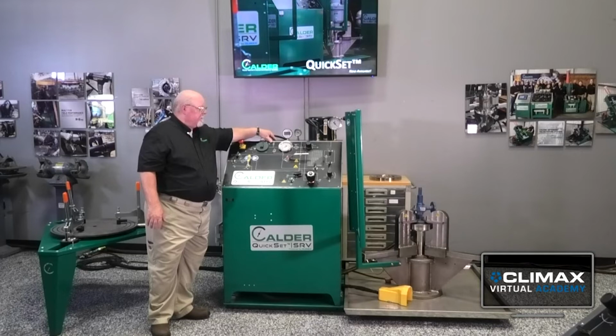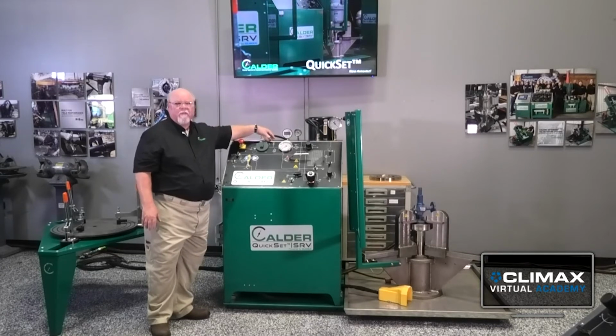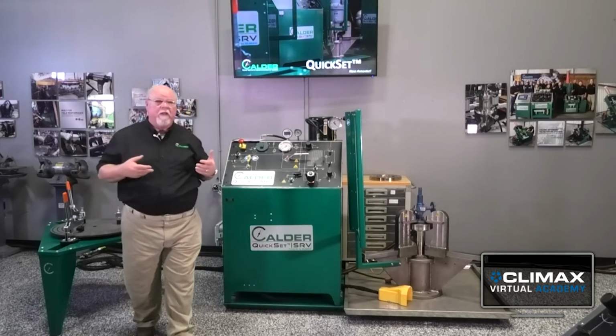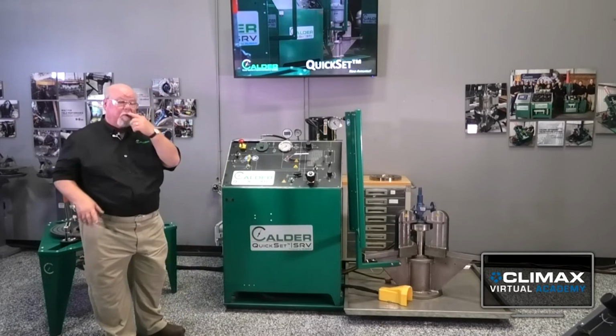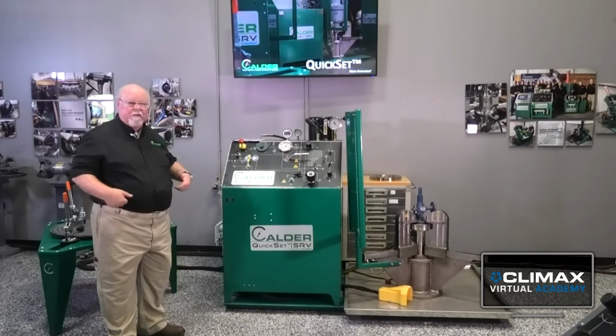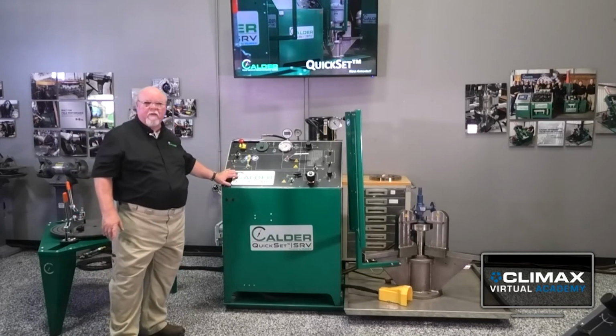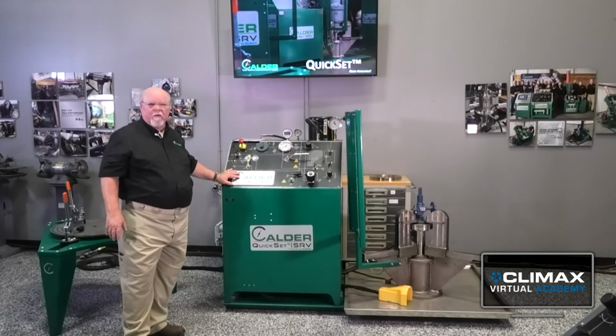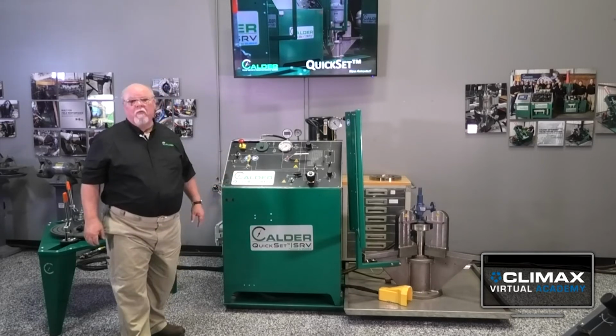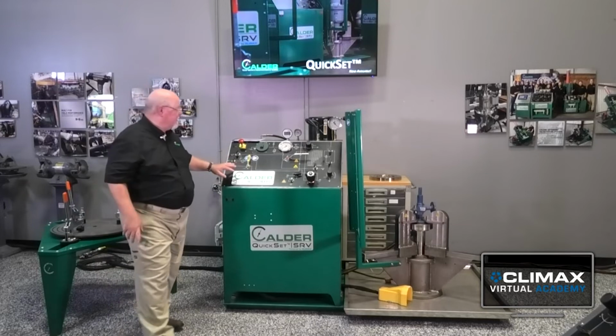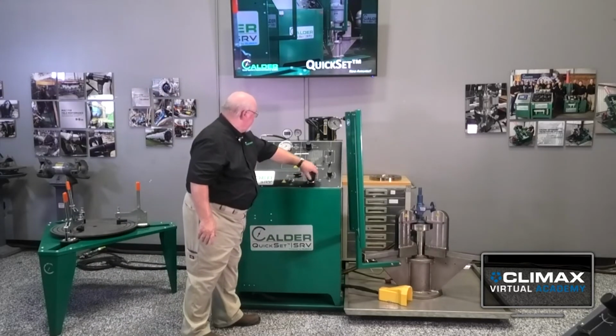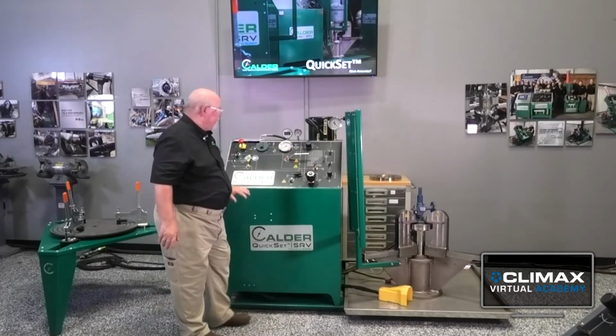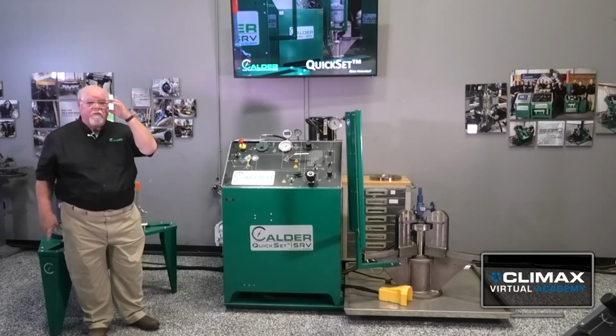As you can hear from the test, there's plenty of pressure to get it off the seat, and then it holds the valve open for a while. Again, this particular unit is set up with 5 gallons and a 1-inch feed line, so there's adequate volume to pop and test that valve. Okay, with that, let me isolate the test stand, and then we'll go to the question and answer period.